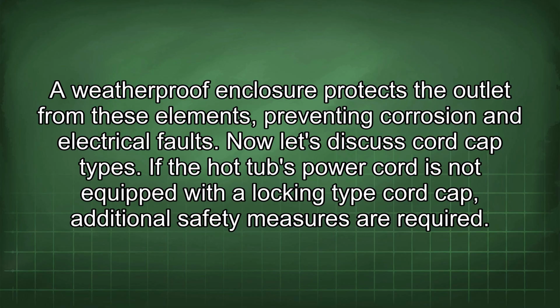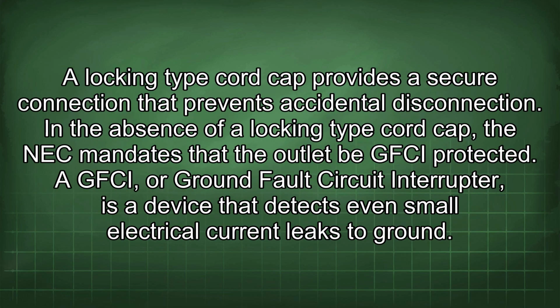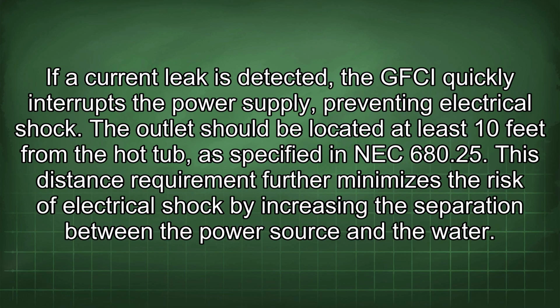Now let's discuss cord cap types. If the hot tub's power cord is not equipped with a locking type cord cap, additional safety measures are required. A locking type cord cap provides a secure connection that prevents accidental disconnection. In the absence of a locking type cord cap, the NEC mandates that the outlet be GFCI protected. A GFCI, or ground fault circuit interrupter, is a device that detects even small electrical current leaks to ground. If a current leak is detected, the GFCI quickly interrupts the power supply, preventing electrical shock.